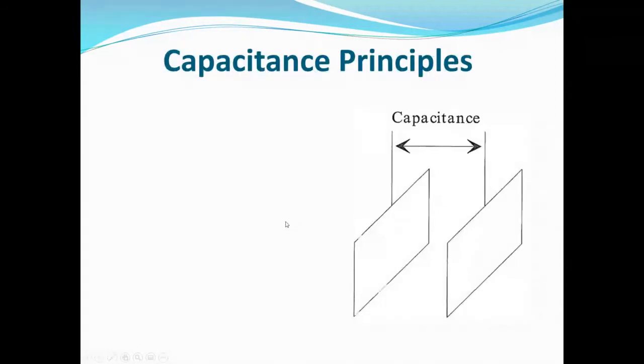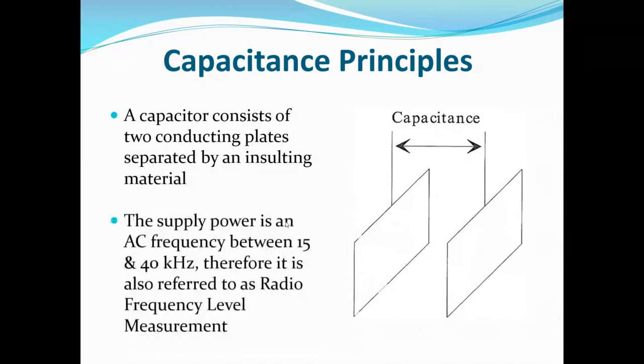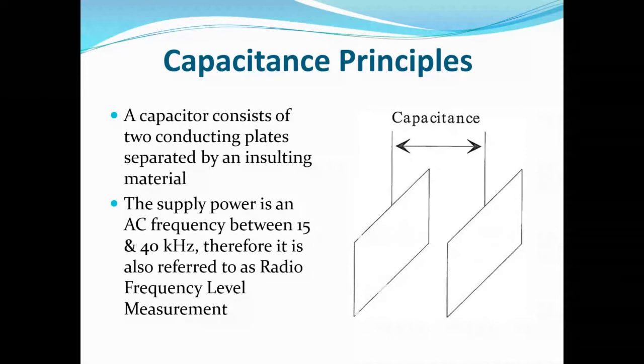Here's the parallel plate style capacitor — two plates with AC voltage applied between them that causes ions to go back and forth. Process medium goes in between. When the tank is empty, it's air between the plates. When the tank is full, there's typically a fluid, or possibly a solid, in between these plates. Whatever that material is will have an effect on the capacitance generated between the plates. That's the science behind it — AC frequency between 15 and 40 kilohertz, which is why capacitance is sometimes referred to as radio frequency level measurement.